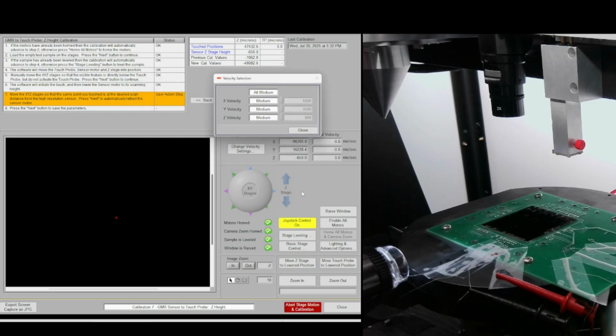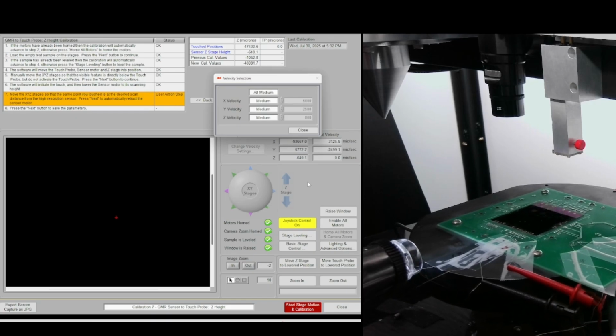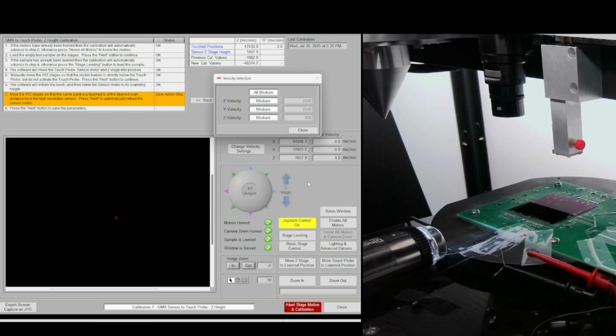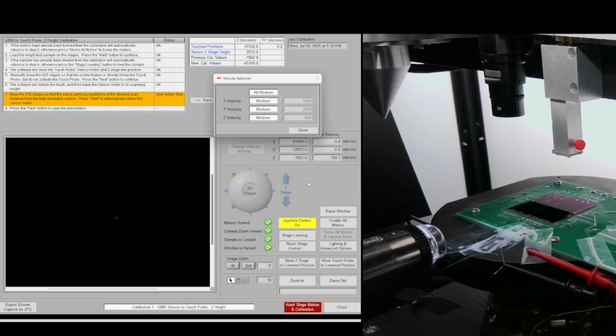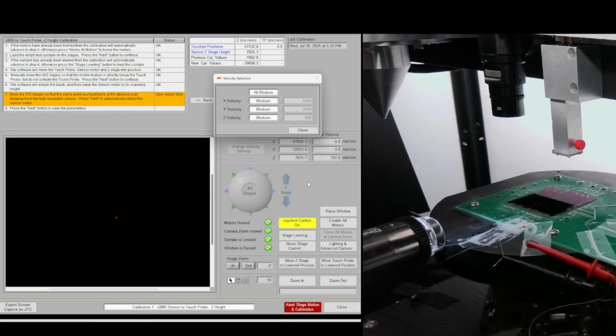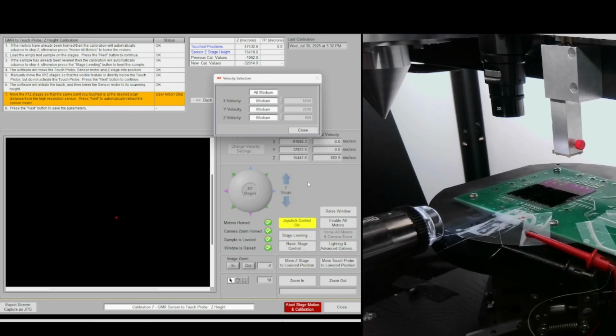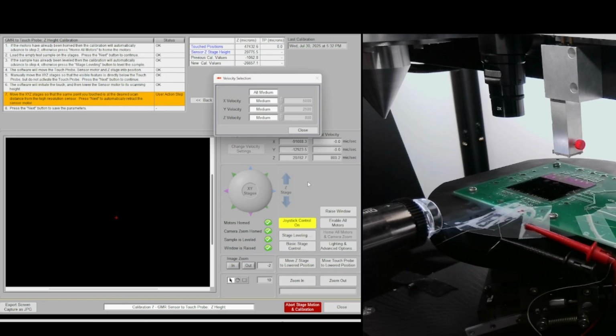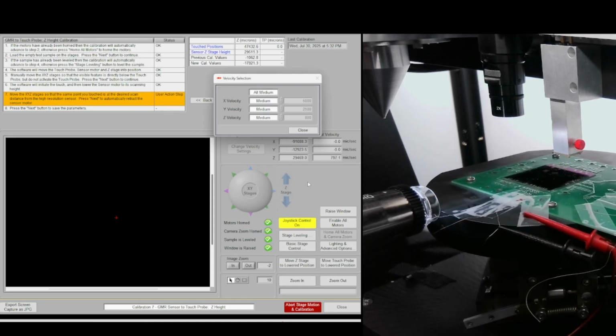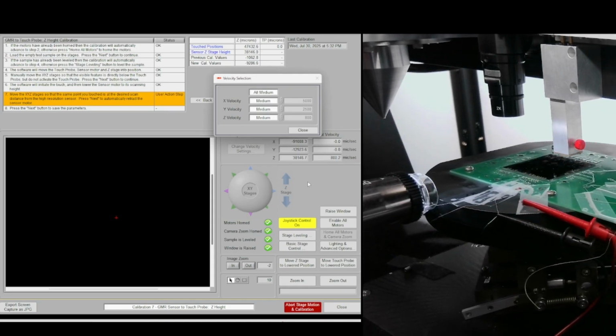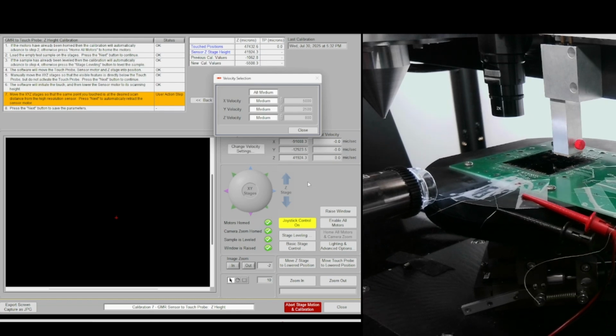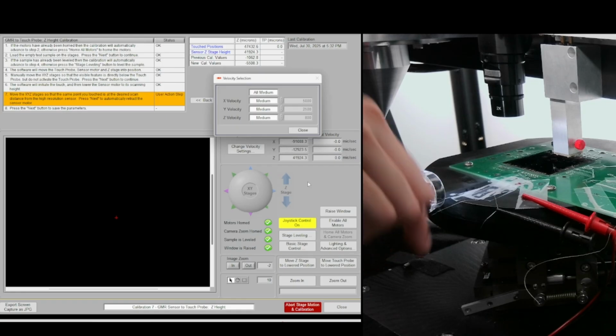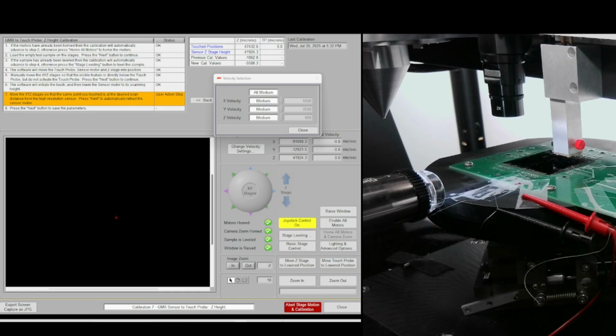In the following step, the GMR is lowered. The goal here is to bring the GMR to the exact location where the touch probe made contact with the sample. Using the joystick, I carefully raise the stage. As the GMR approaches the sample, I reduce the velocity to avoid any risk of collision. At this point, I use the Dino-Lite camera to closely monitor the GMR. I position the camera to clearly see both the GMR and the cantilever, watching for any excessive flexing.